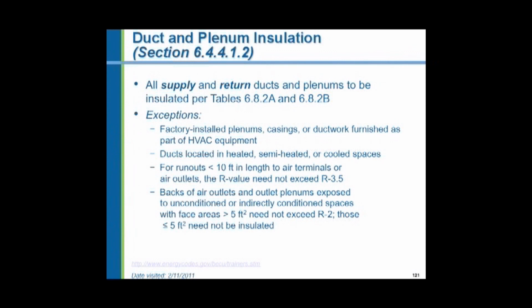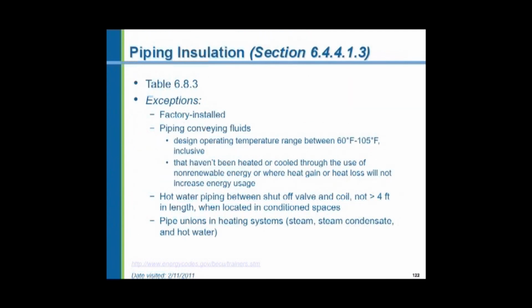But they have no ceilings. They are open roof trusses. Piping is exposed, wiring, conduit, and ductwork. So in that case, you do not need to insulate the duct. Short runouts of duct to air terminals do not need to be insulated. And again, another exception for the back sides of air outlets and plenums exposed to unconditioned spaces if it's just a little bit, less than 5 square feet. Piping insulation. Piping carrying fluids below 60 degrees Fahrenheit and above 105 degrees Fahrenheit have to be insulated. The exception to that is any water that might be solar heated, any kind of naturally heated or cooled water, maybe lake or river water where you're not using fuel to heat or cool it. You need not worry about the insulation.